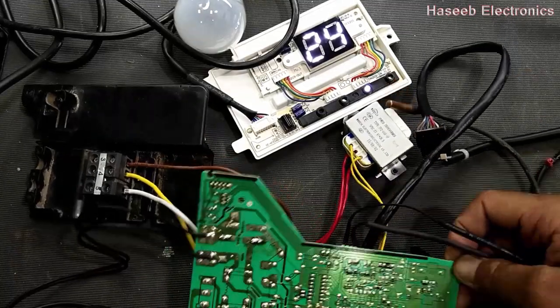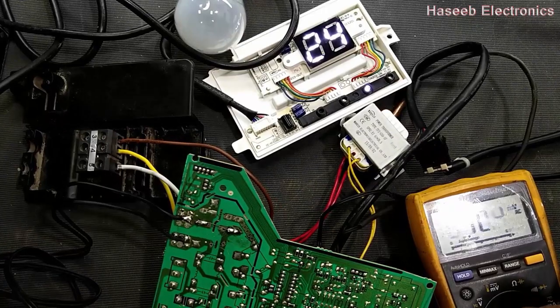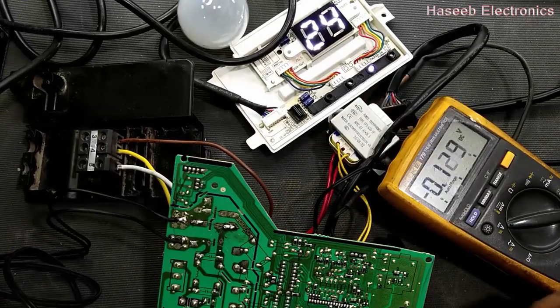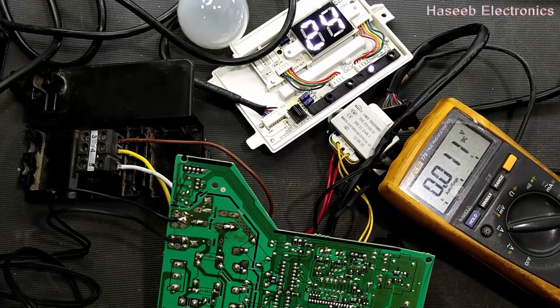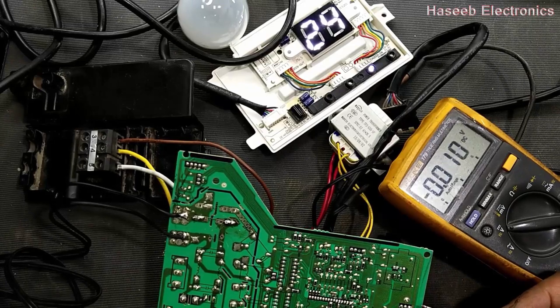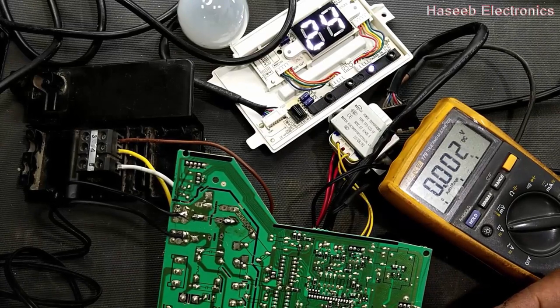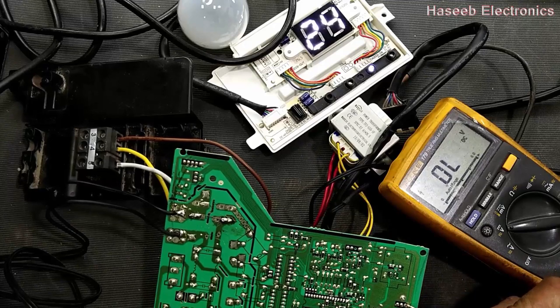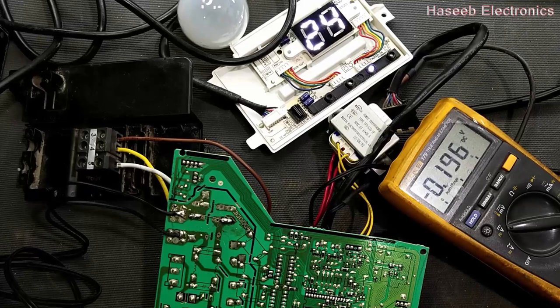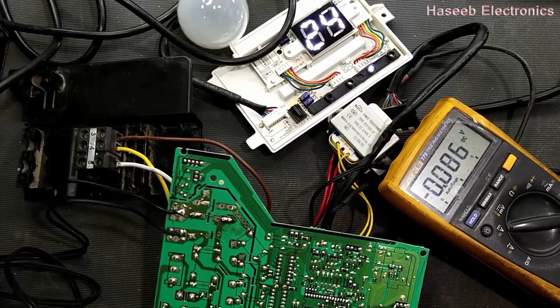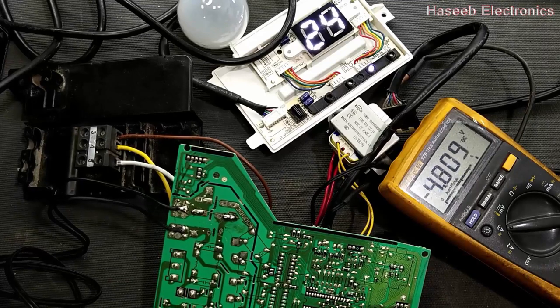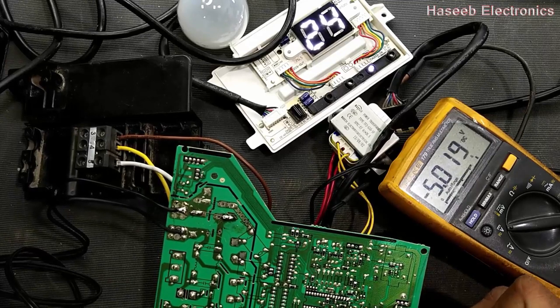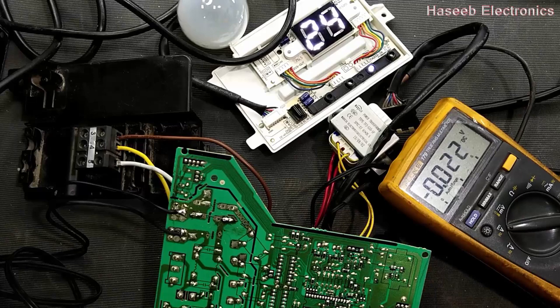Now I will give the checkpoints, how we can verify the function. Set multimeter to DC. At first, we have to check the DC voltage. Here we have 15 volts. Check the right side pin and the center pin. So it is 5 volts. We have 5 volt regulated.